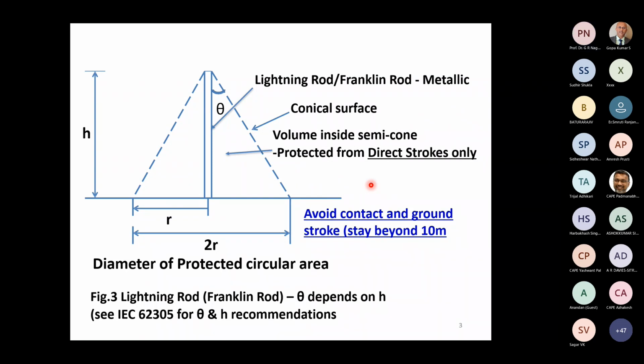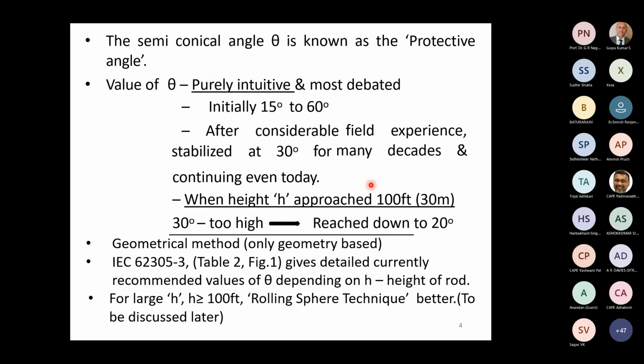Now, the angle theta was originally purely intuitive. That's why we call it geometry. It's only a cone of some angle theta at the vertex. It's purely intuitive, and it was highly debated at one time. It started from 15 degrees to 60 degrees, a huge range. After considerable field experience for many, many decades, it stabilized at 30 degrees. So for many decades, it was thought that if you provide a rod, the area with 30 degrees semi-conical angle at the tip, the circular area at the bottom is protected from direct strokes. That is the basic principle of the geometric method.